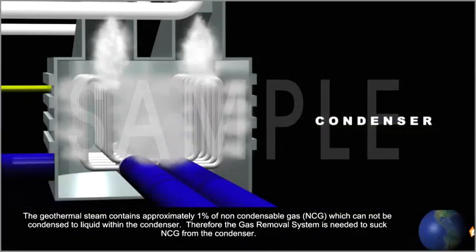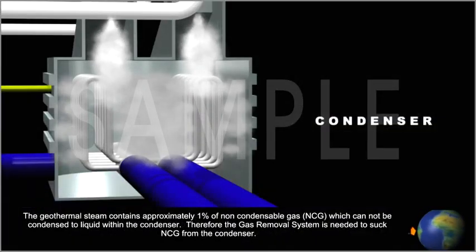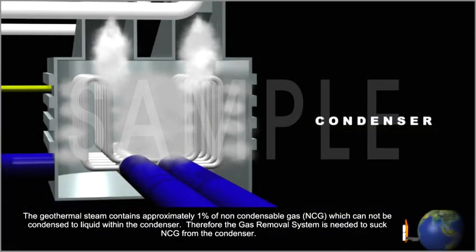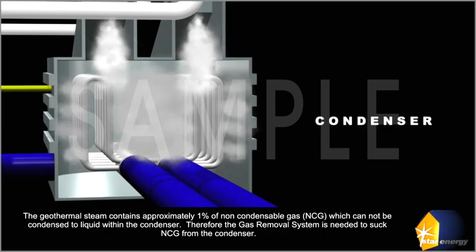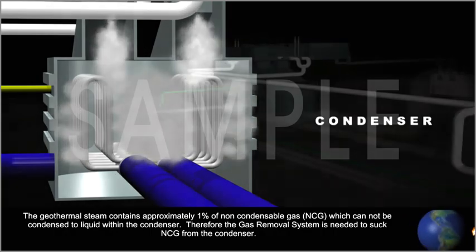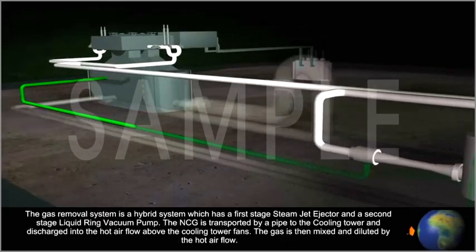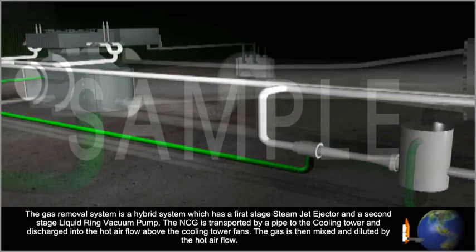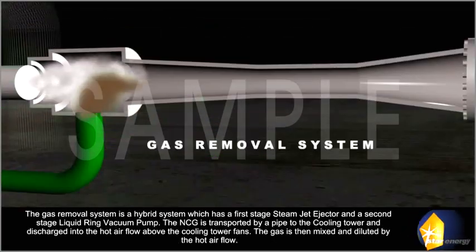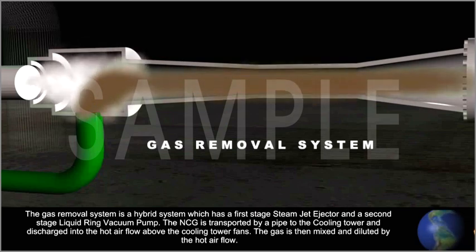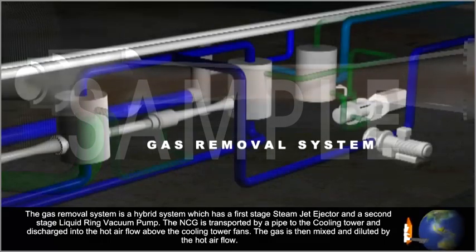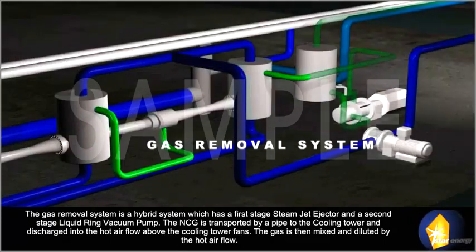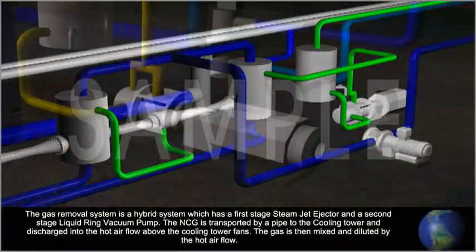The geothermal steam contains approximately 1% of non-condensable gas (NCG), which cannot be condensed to a liquid within the condenser. Therefore, the gas removal system is needed to suck NCG from the condenser. The gas removal system is a hybrid system which has a first-stage steam jet ejector and a second-stage liquid ring vacuum pump. The NCG is transported by a pipe to the cooling tower and discharged into the hot air flow above the cooling tower fans. The gas is then mixed and diluted by the hot air flow.